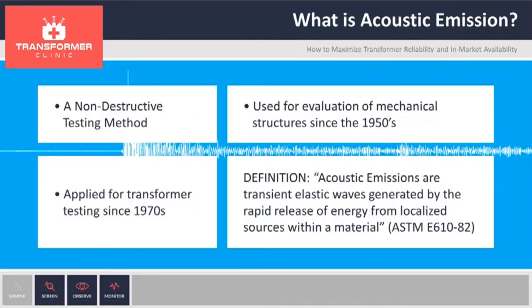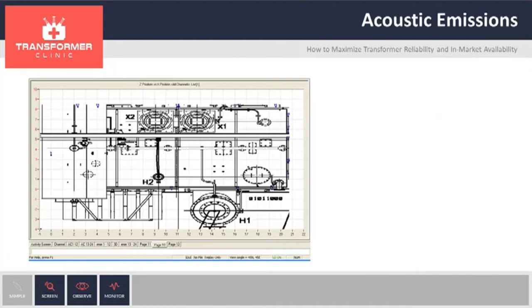One of the techniques I'm going to be talking to you about is acoustic emission. Acoustic emission has been around since the 50s. It has been used for mechanical evaluation of structures, looking for cracks, corrosion. In power transformers, it has been used since the 70s. It was applied by Westinghouse during induced voltage tests and has been evolving since. Here we're looking at the top view of a transformer. We do this test with the transformer in service, which is one of the advantages of the technique.